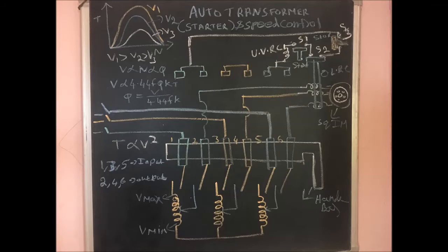Normally, how do we start? With the help of the start switch. That's the push button. If you push it, the motor will run. What about the stop button? If you push the stop button, the under voltage release coil gets demagnetized. Automatically the handlebar moves downwards and switches 1, 2, 3, 4, 5, 6 open. Everything is safe. So by the auto transformer we can start the motor, stop the motor, and protect the motor. It is a very useful starter, but it is costlier due to the windings.